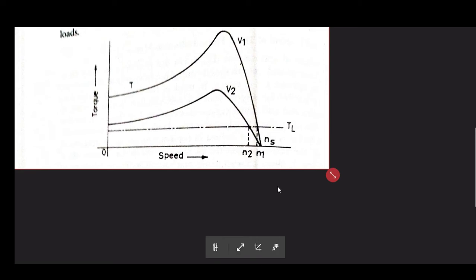So in case of DC machine, the torque remains constant from 0 to this final stage, because the basic fundamental understanding of a DC machine lies on the fact that if you vary voltage, it doesn't alter the steady state armature current. The reason behind this difference between DC motor and induction motor is that the DC motor relies on generated voltage, dynamically induced voltage, and in case of your induction motor, the operation depends on transformer EMF.